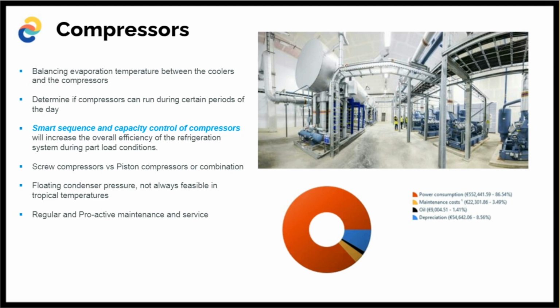As I said before, what times of the day the compressors can run, and certainly a smart sequence and capacity control system. And we have some nice solutions for that, and my colleague is going to point them out, because we need to prevent compressors from running in part load, because part load makes the compressors a little bit inefficient.